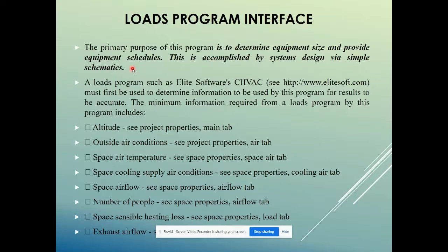As for the loads, you can calculate them first by using certain software such as Elite Software, CHVAC. And the calculated load can be imported into the HVAC solution software. From the load software, you can transfer the altitude, outside air conditions, space air temperature, space cooling supply air conditions, space airflow, number of people, space sensible heating loss, etc.